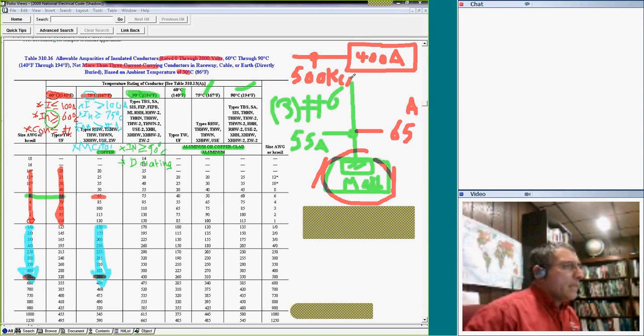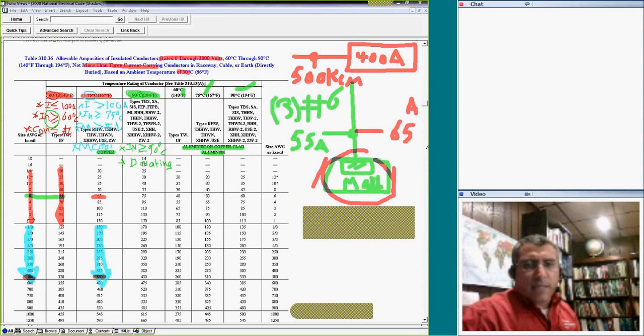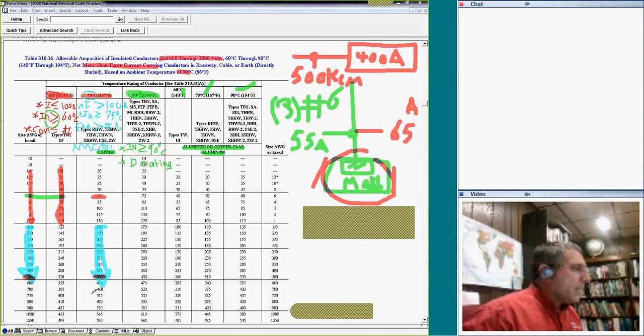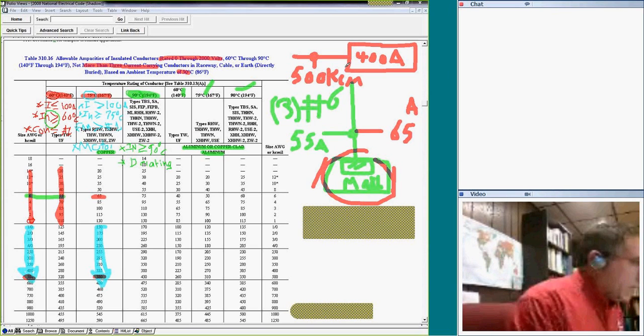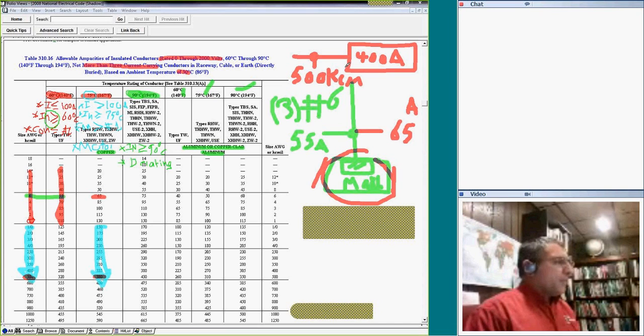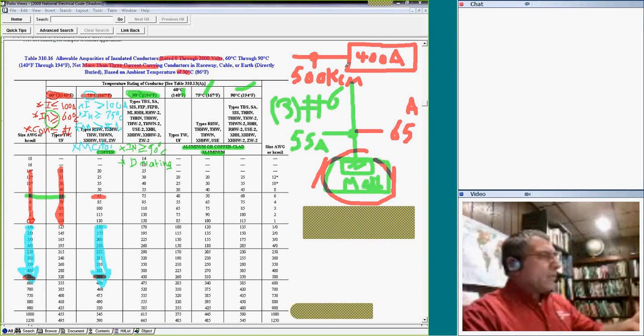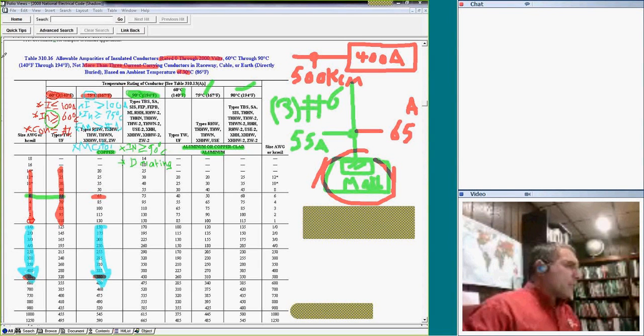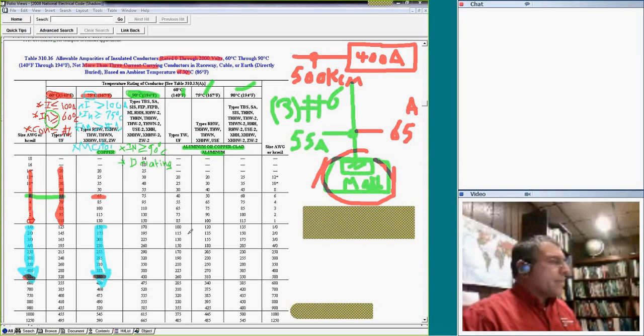500 KCM. Now I'm sure some of you guys are looking at me and saying, Chad, but look, 500 can only carry 380. They use this because the next overcurrent protection device is 400. That's okay. In a case like this, the current is 380, but the 400 amp, is this okay? Yes. If it's based on the rules in the code, that says if the overcurrent protection device is the next standard, then no problem. What's the next standard overcurrent protection device? 400, right? So that's okay. And so use 500 KCM. But where did I go? I went to the 75. Any questions?